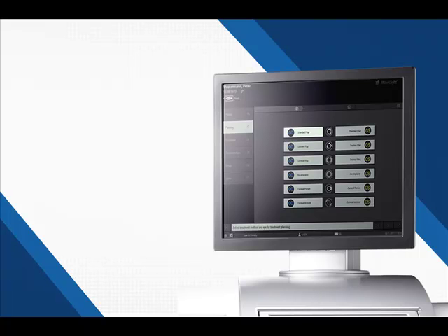So this is the difficulty in a hard surface interface. They're cheap, they're easy to make, but here's a larger image of these corneal wrinkles. The top image is the first generation of patient interface, which was a hard plastic surface. And as you magnify the image, you can see that it did cause wrinkles on the backside of the cornea, and that led to imperfect performance further deeper in the eye. Softfit is a proprietary soft contact lens. It's part water, it's part silicone. And when we use Softfit to dock onto the eye, those wrinkles are gone.